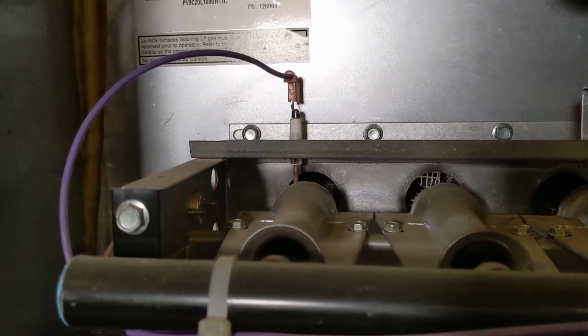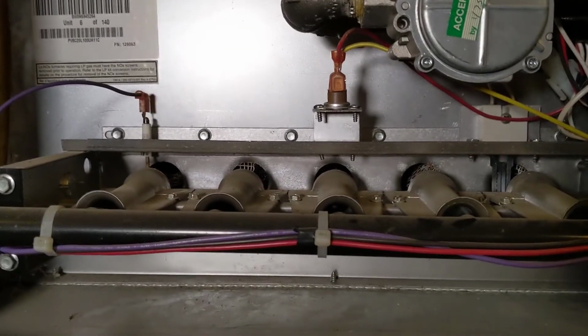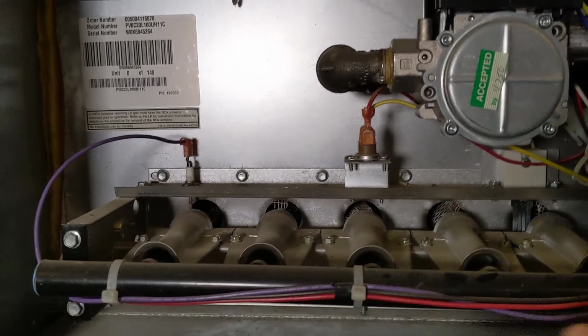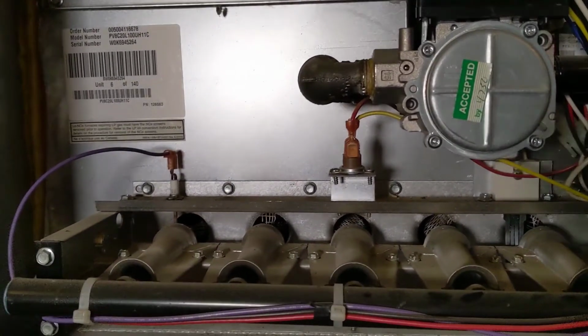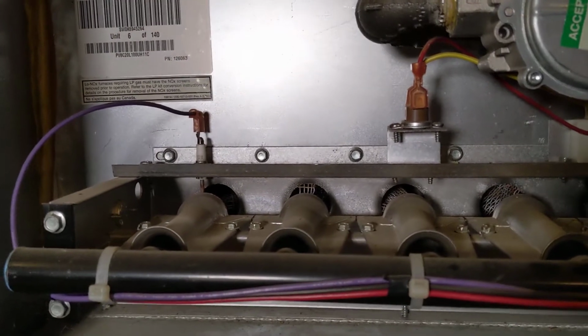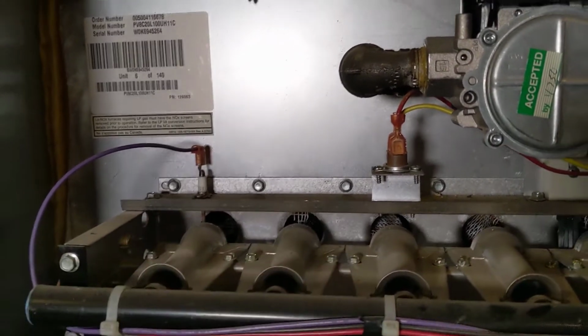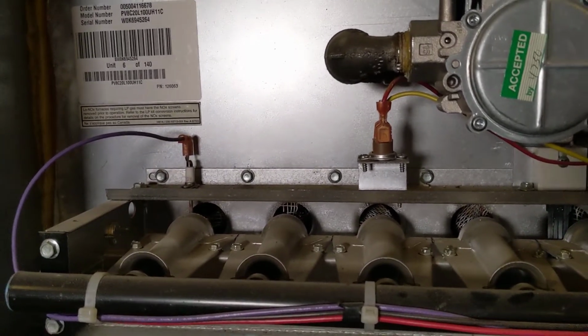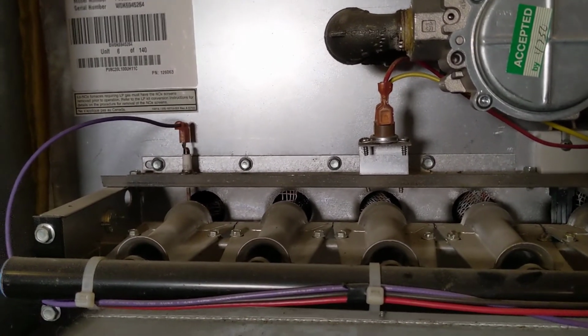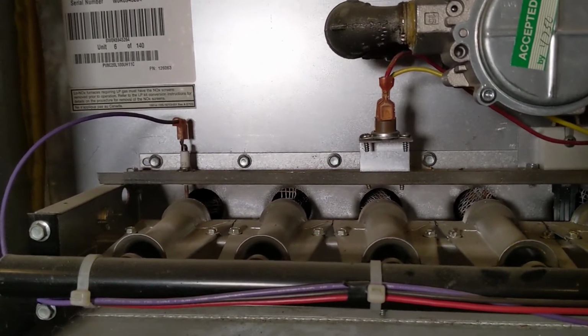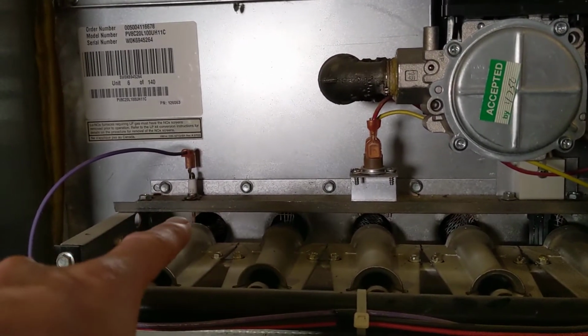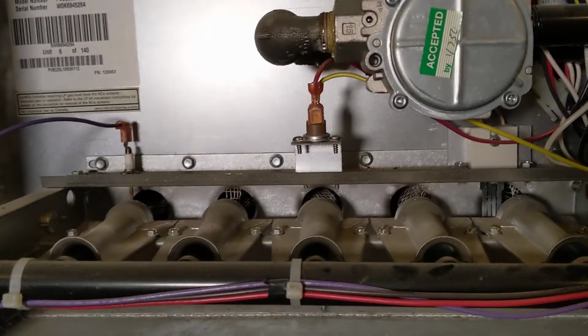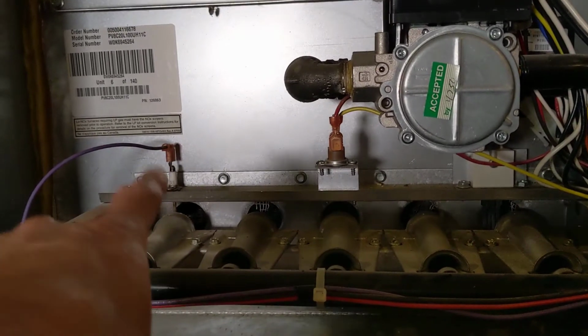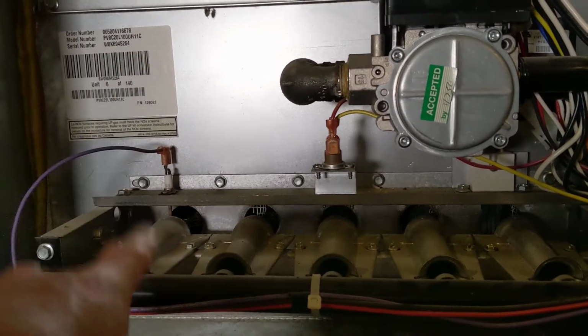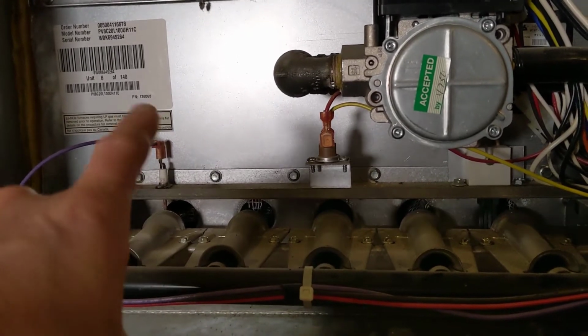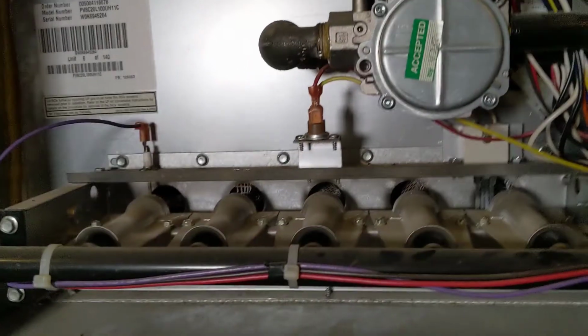It's specifically on the last one because it's detecting if there's a flame or not, and being on the last one makes sure that it's all the way at the end and we have all of our burners firing. If there is no flame, then the flame sensor will tell the board, don't run. The reason for that is obviously safety. If we don't combust our gas, then we just have a gas leak, and that's bad. So that will tell the board to shut off the gas valve because we don't have proper combustion. That's a common component, and I'm going to show you how that works and how to clean it, because that's a very common problem with furnaces shutting off and not operating properly.